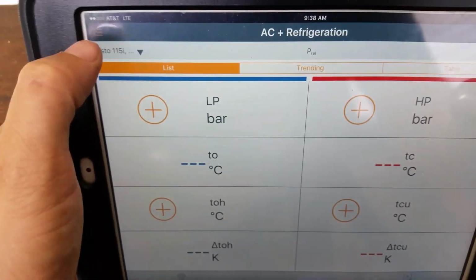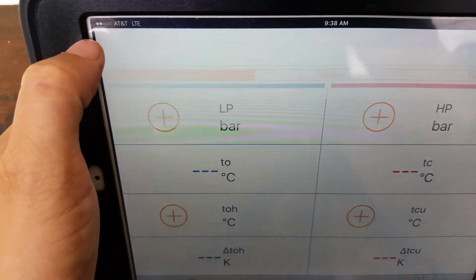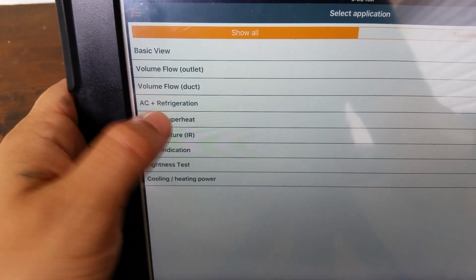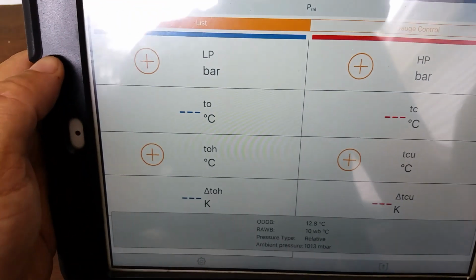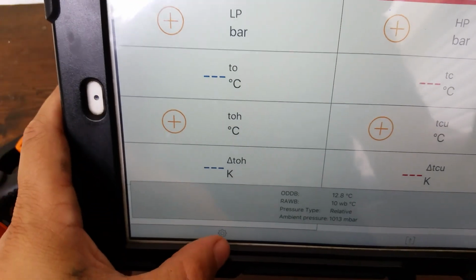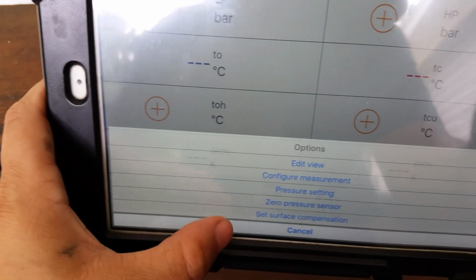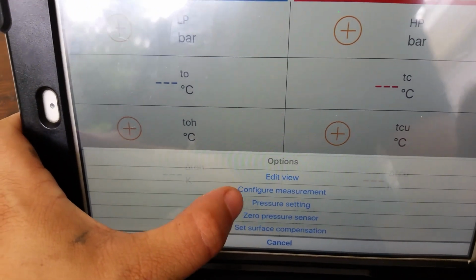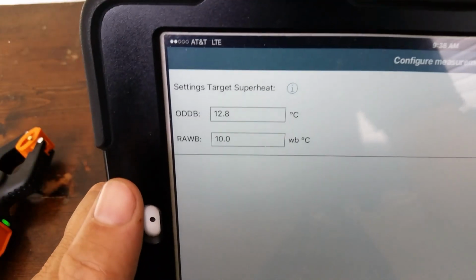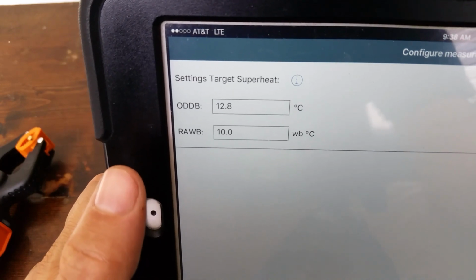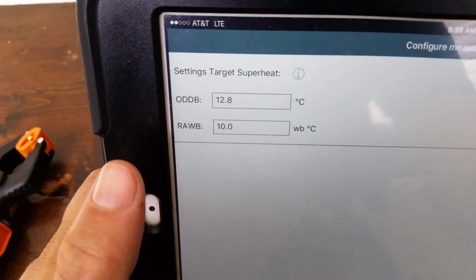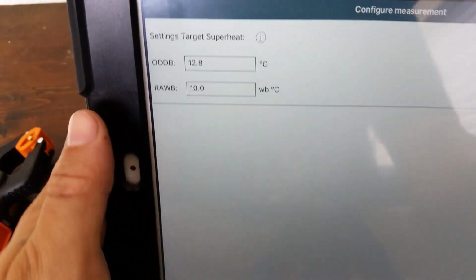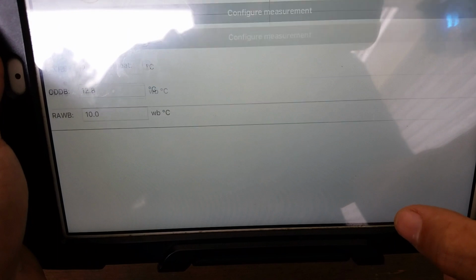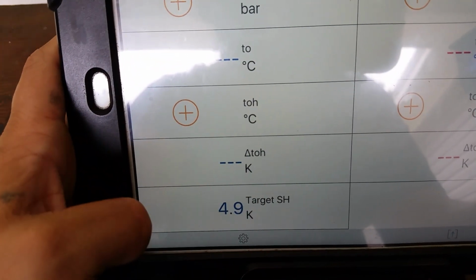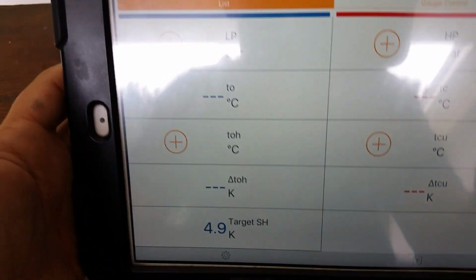If we go back, the target superheat is a very similar screen, almost identical, but if you click the gear, you can go to configure measurement, and it gives you an option to enter your outdoor dry bulb and your return air wet bulb. Those give you your calculations for superheat. So if we just leave those numbers in and click OK, you can see it gives us a target superheat down there. Very, very simple.